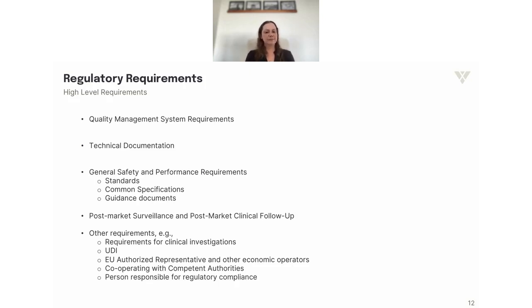In the MDR, you have a list of general safety and performance requirements. Now, this is a list which is meant to capture all types of devices, and I'll go into this in more detail shortly as well. But you need to go through these in detail and determine how you're going to comply with them if they apply. And if they do not apply, you have to have justification. And there are different methods of complying with the requirements. Standards tend to be the preferred method. There are also common specifications. There are very few at the moment, but you want to be sure that there are none that apply to your device. There are also guidance documents out there. Not quite as many as those of you who are familiar with the FDA are used to, but there's quite a few, and there will most certainly be some that apply to you.